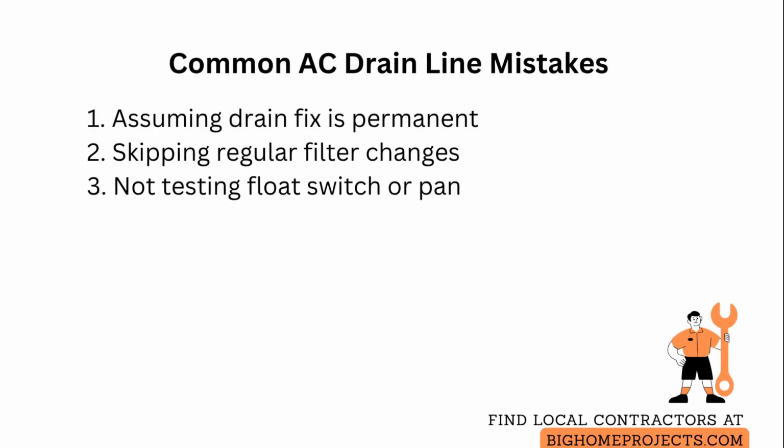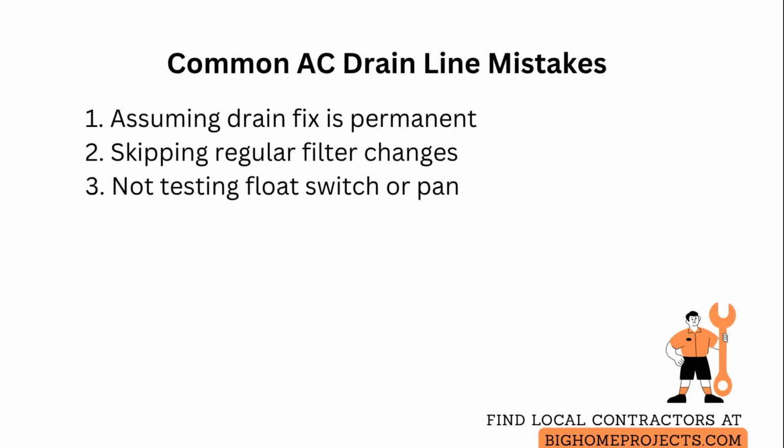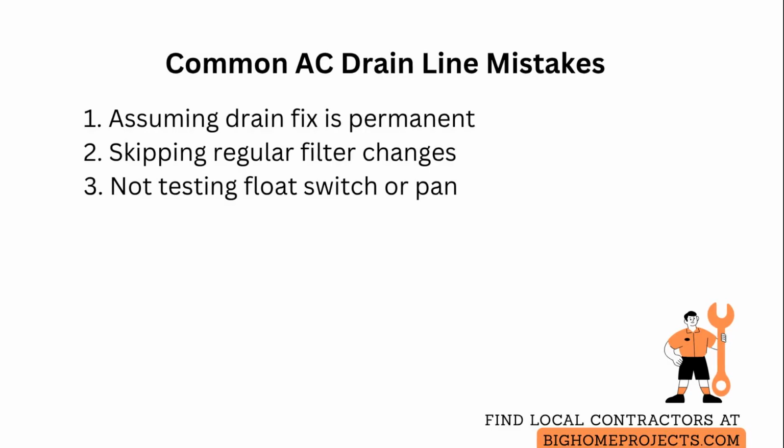People also forget to test the float switch or to clear the condensate pan drain pathway. Test the float during every service and clear the pan with a manual flush to verify proper flow rather than waiting for a leak.